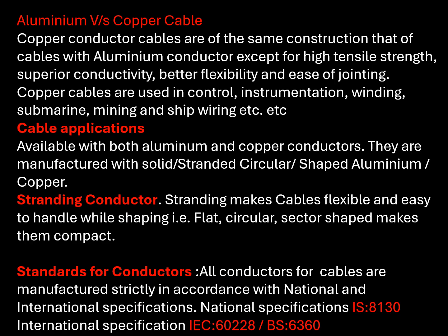Cable applications are available with both aluminum and copper conductor. They are manufactured with solid, stranded, circular, shaped aluminum and copper. Stranding of conductor is necessary for the reason that the current mostly flows in the exterior portion of the cable. The interior portion is of no use. So we strand them to increase current carrying capacity. Stranding makes the cable flexible and easy to handle while shaping.